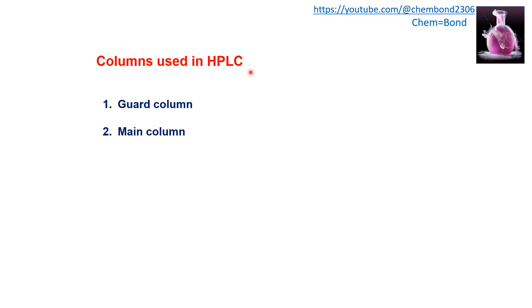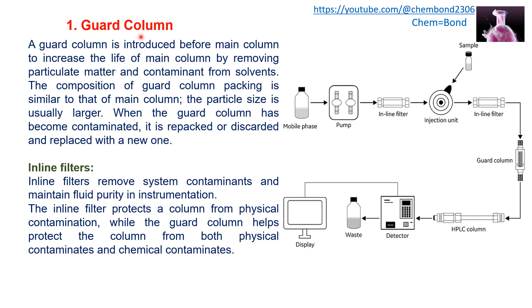There are two types of columns used in HPLC: the guard column and the main analytical column. The guard column, also known as the protective column, is introduced before the main column to increase the lifetime of the main column. If particulate material or contamination present in the mobile phase moves toward the HPLC column, it can damage the HPLC packing material by reacting irreversibly with it.